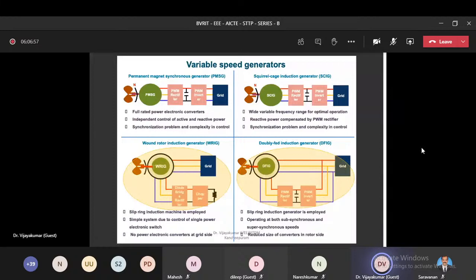At the same time, whatever converters you are connecting at the rotor side, the converter ratings are 30%. Why are the converter ratings 30% as compared to the top two topologies? In the top two topologies, the converter ratings are equal to the machine rating. If it's a 1 megawatt machine, then at least you have to use a 1 MVA or 1.2 MVA converter rating. But here, for a 1 megawatt machine, you can use a 300 kilowatt power rating of the converter. What's the reason? Do you have any reason?